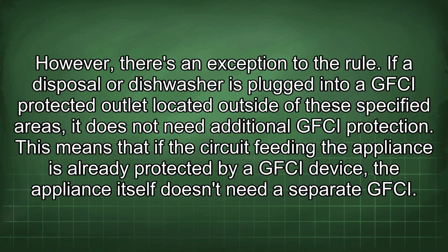However, there's an exception to the rule. If a disposal or dishwasher is plugged into a GFCI protected outlet located outside of these specified areas, it does not need additional GFCI protection. This means that if the circuit feeding the appliance is already protected by a GFCI device, the appliance itself doesn't need a separate GFCI.